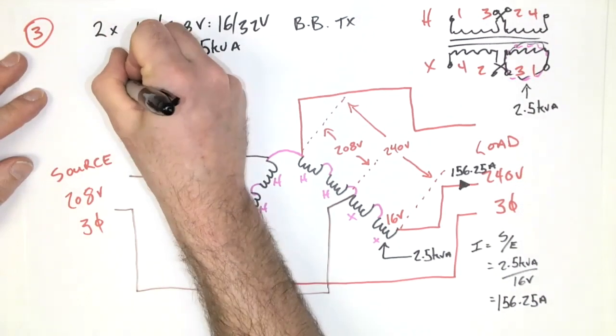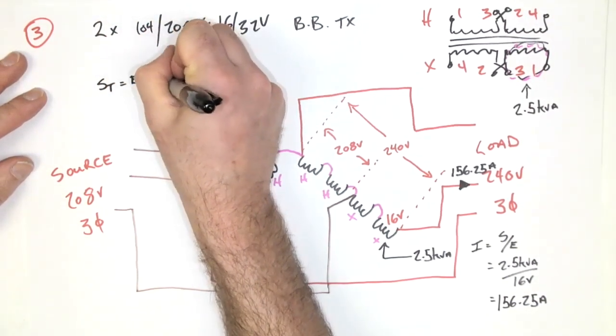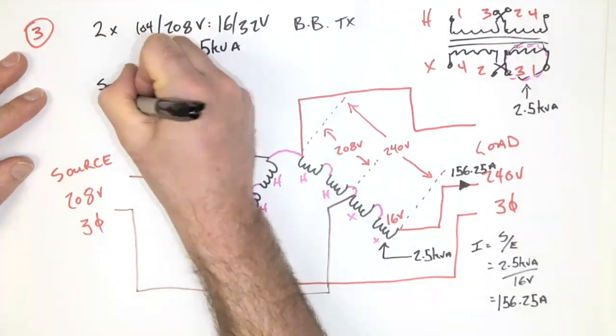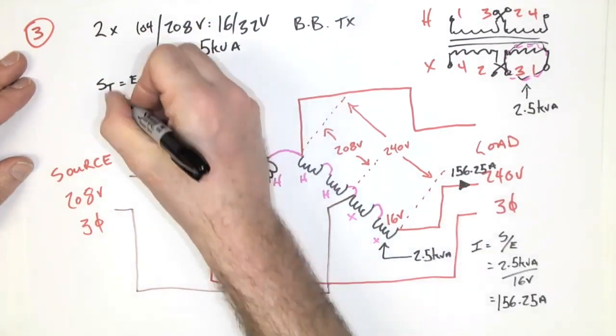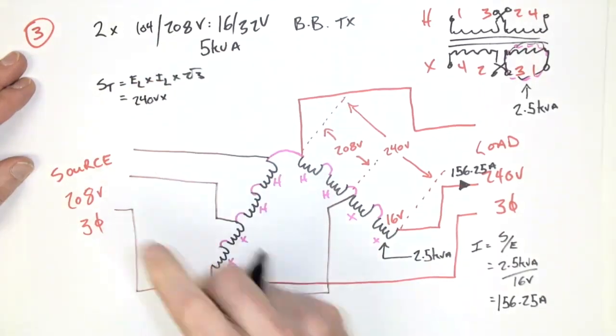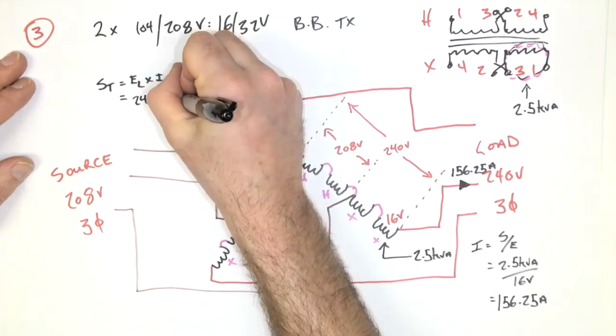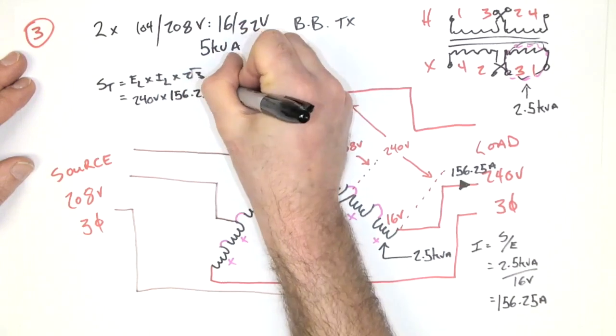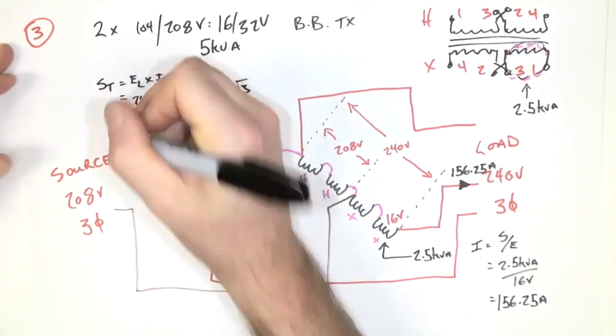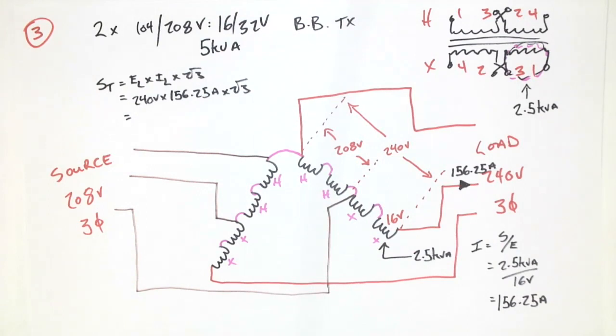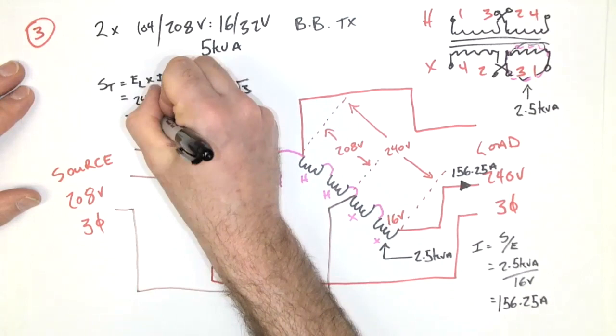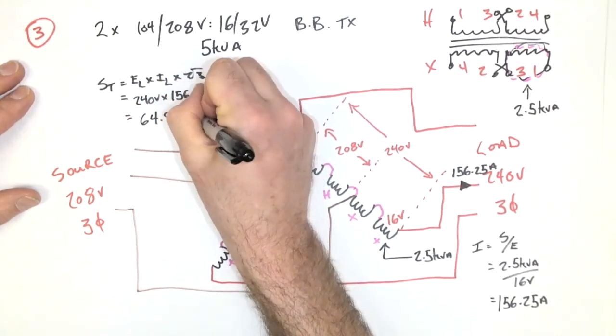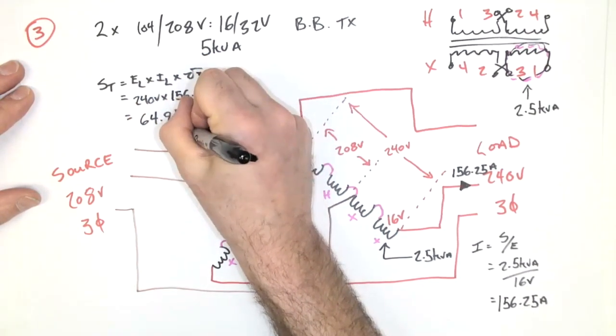Well, let's go ahead and calculate the total kVA of the system. That would be S total is equal to E line times I line times root 3. We get an E line voltage of 240 volts, an I line current of 156.25, and of course, root 3. So let's calculate it all out. 240 times 156.25 times the square root of 3. And I get, oh, look at that, 64.95 kVA. Wow, that is a whopper.